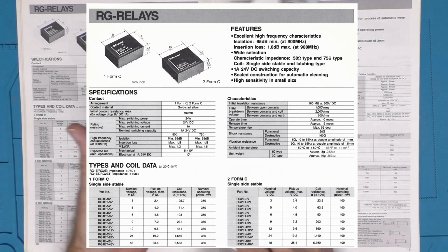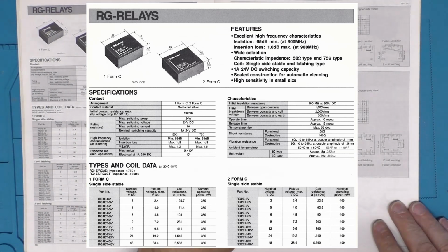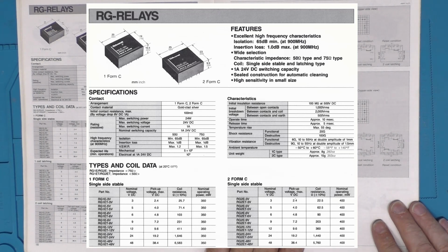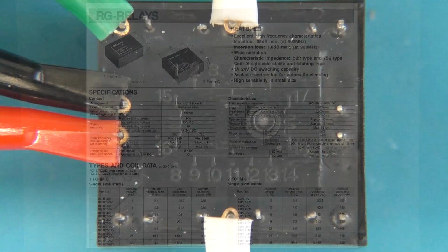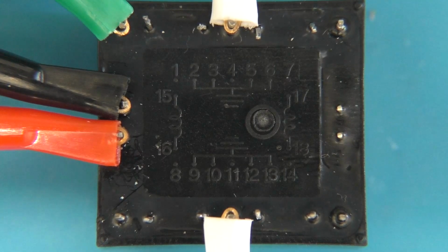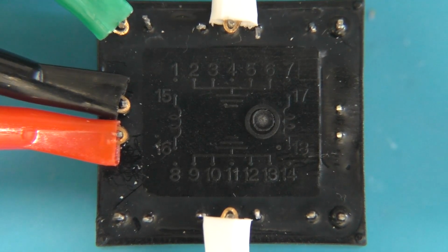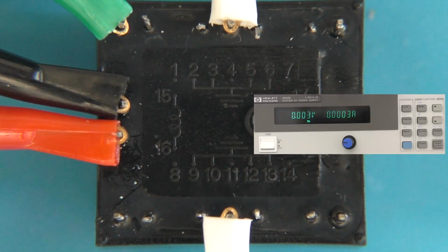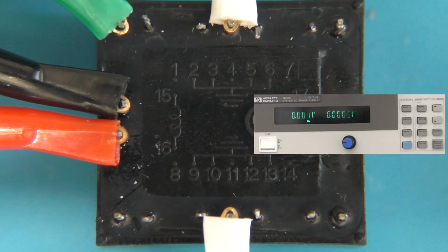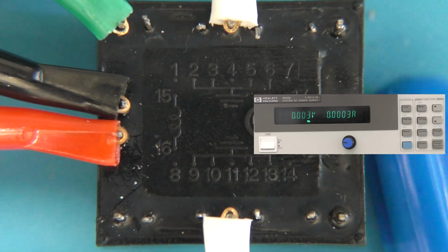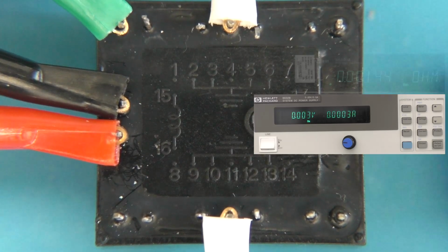Unfortunately, I cannot see any information regarding the H11, and nothing online either. This may be a special part for HP. We will need to check it out further. Let's put this relay under test. We have the relay coil pins 15 and 16 hooked up to a power supply with a suitable back EMF suppression. The center pin of each pole, pins 4 and 11, are connected to DMM positive.